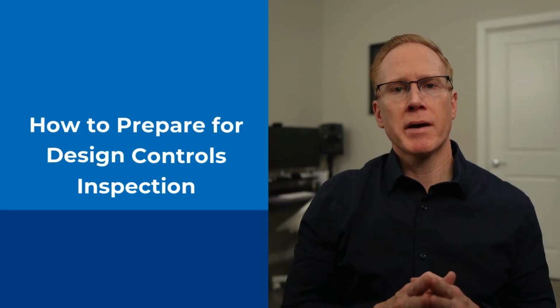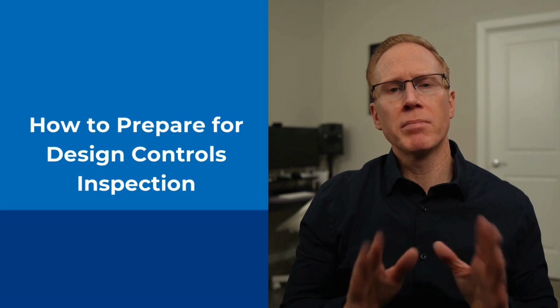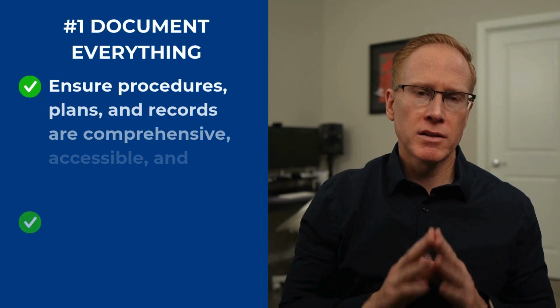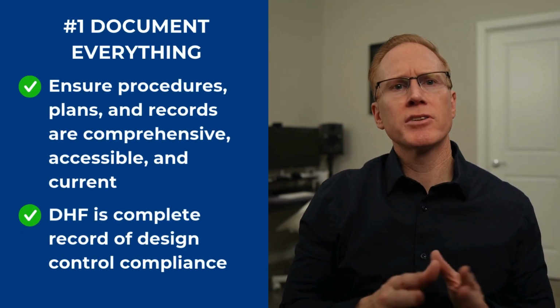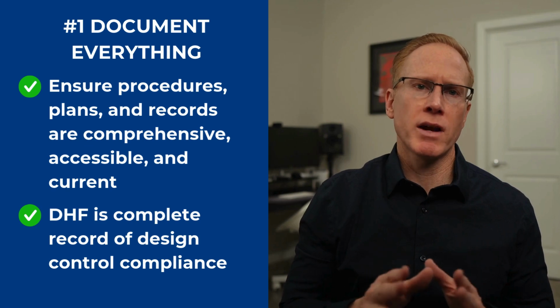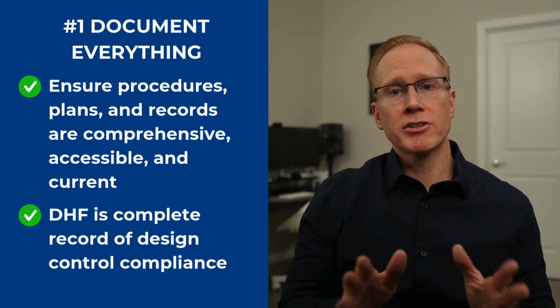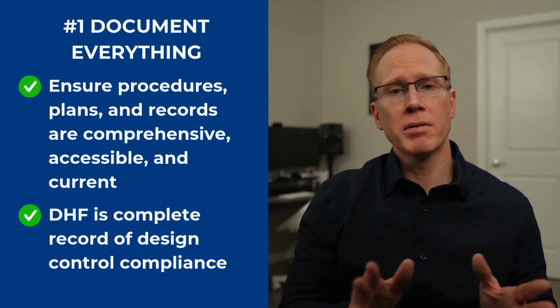To prepare for an inspection, you need a strategy that ensures compliance and minimizes risk. Here's how to do it. Number 1, document everything. Ensure design control procedures, plans, and records are comprehensive, accessible, and current. Your DHF should serve as a complete record of compliance activities.